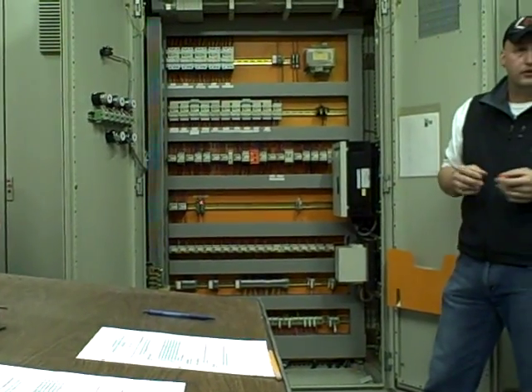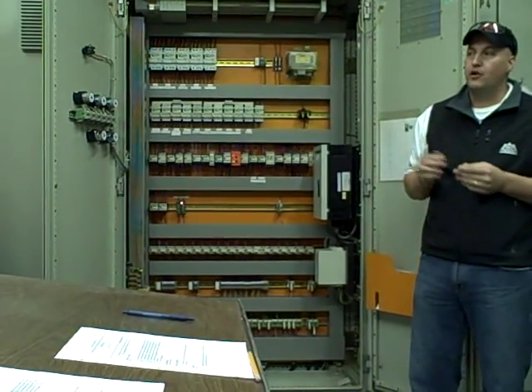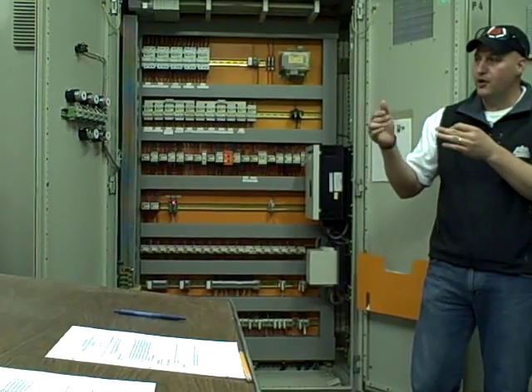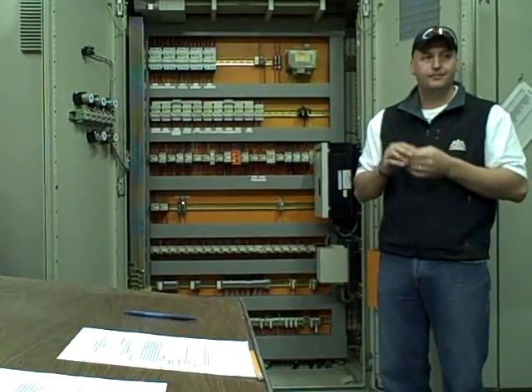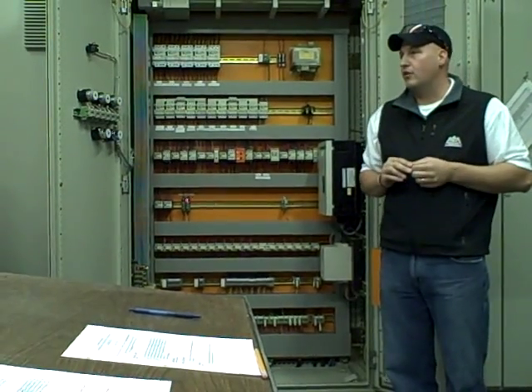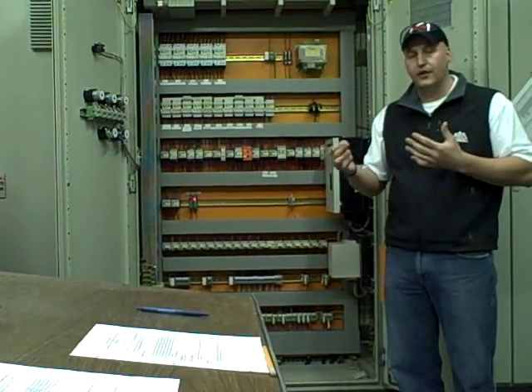Now in the brewing industry, you don't see a lot of flow meters — you probably have 12 throughout the brewery. That's one thing about beer when it comes out of the brew house: wort loves aeration. It loves air before it hits the yeast. Well, with aeration, flow meters just don't work. You start bubbling up, you'll run into problems, you'll have false readings. So you have to get away from that.